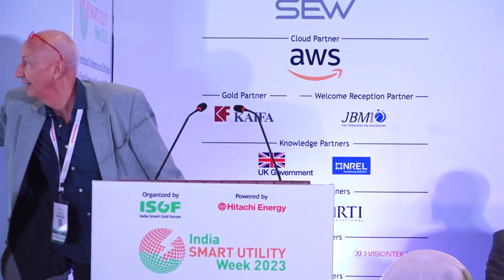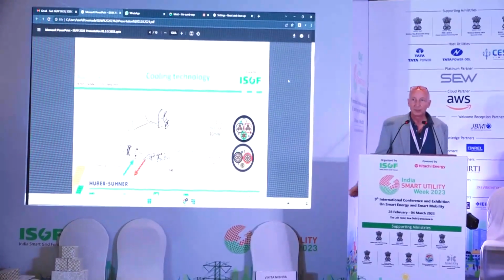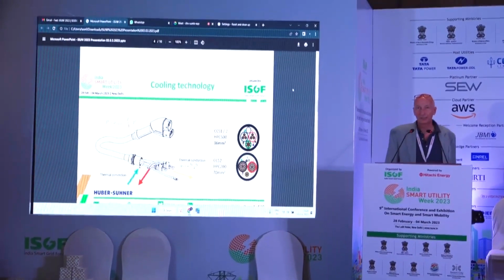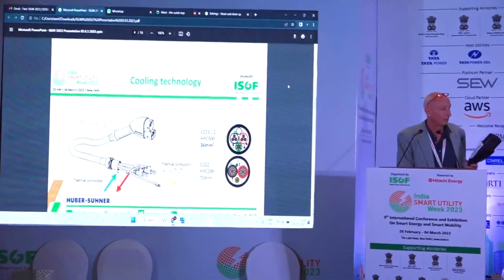Here you just have a picture of how we cool it. The blue arrow shows the cold liquid going through the cable, cooling around the pins on the way back. We're cooling directly on the copper, in between the power lines and the insulation. It's an insulated coolant, so there's no risk even if something goes wrong.